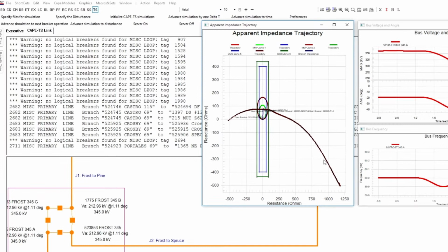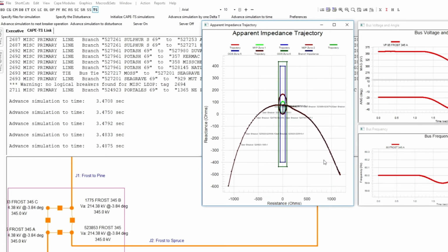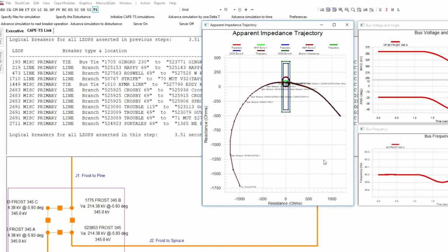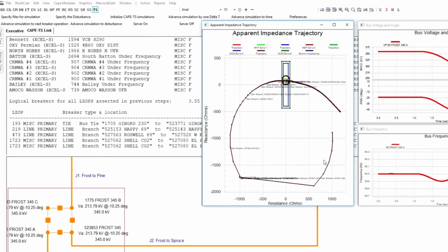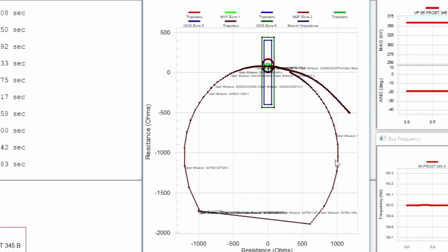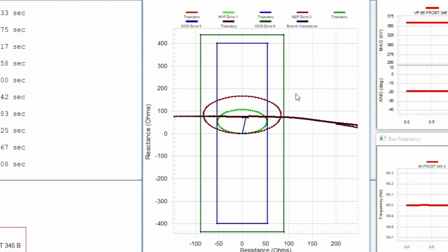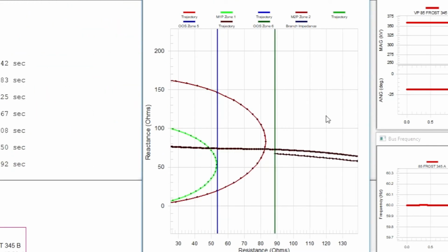actual event. Several under-frequency relays start operating to shed load following the reduction in generation. This is part of the remedial action scheme, which automatically takes corrective actions to try to recover the network. In the second slip cycle, the apparent impedance is traveling faster than the first slip cycle, as the impedance travels a longer distance between two consecutive time steps.